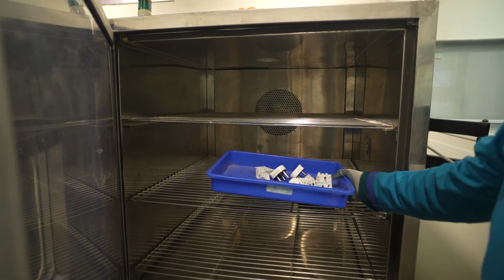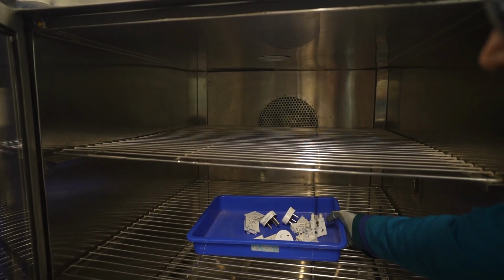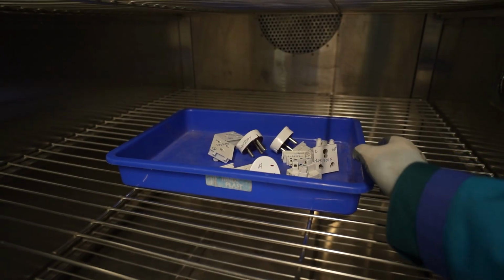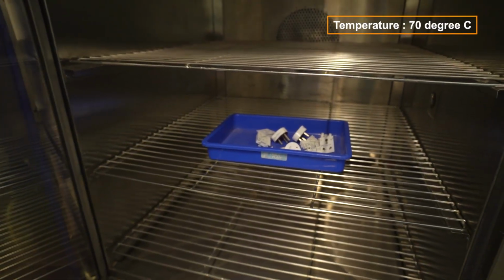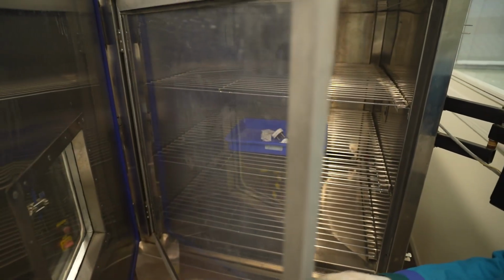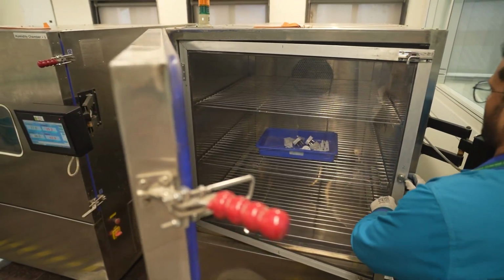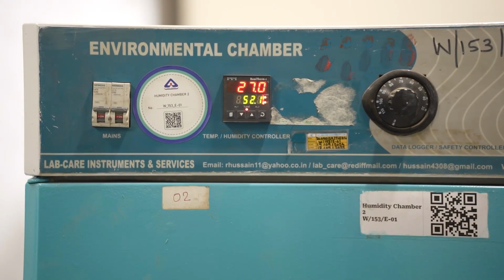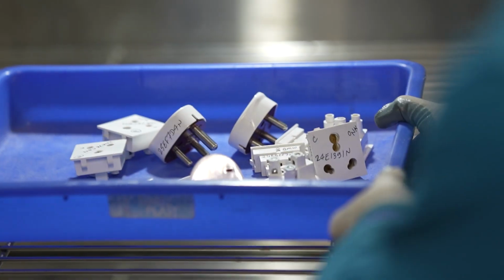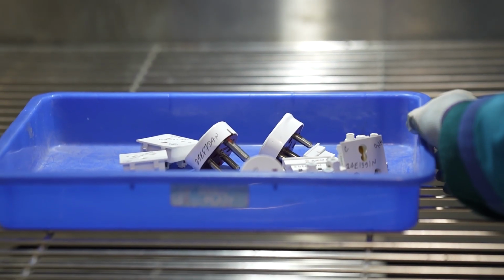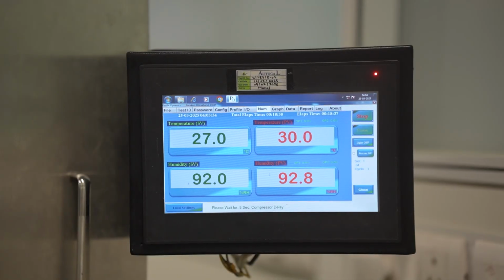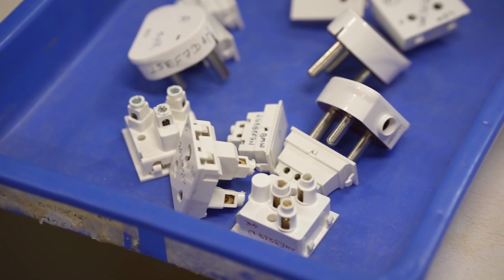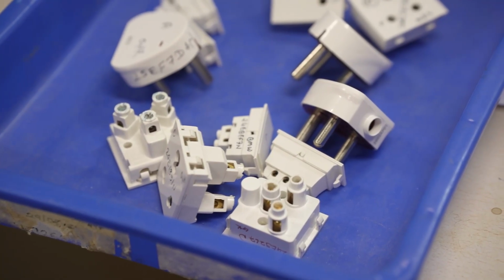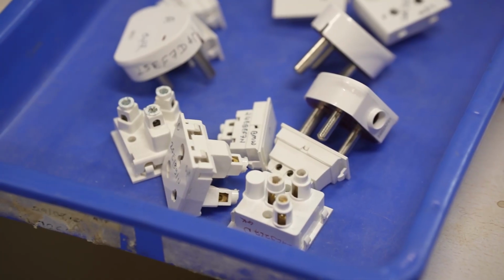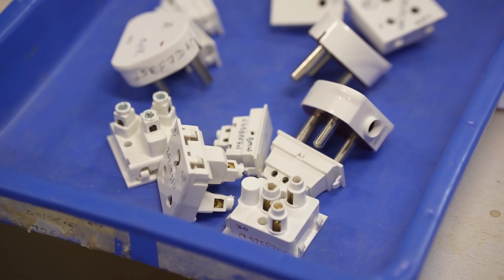Resistance to aging and humidity. Clause 16. The accessories are exposed to aging and humidity conditions that simulate normal usage. The rigidity is evaluated by subjecting the accessories to 70 degrees Celsius in a hot air oven for 7 days, followed by 4 days in a humidity chamber at 45% to 55% RH and room temperature. Additionally, the specimens are placed in a humidity chamber at 91 to 95% RH and room temperature. After testing, the specimen must show no visible cracks, stickiness or greasiness. This ensures the plugs and sockets can withstand prolonged exposure to heat and moisture.